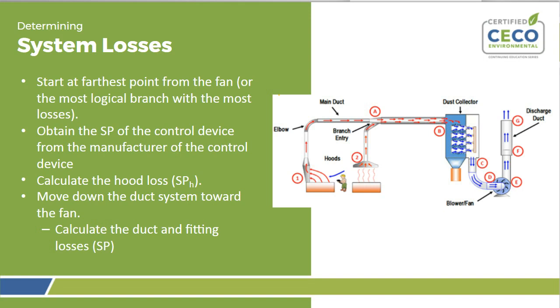It goes out of the clean air plenum of the dust collector into your fan, from your fan to your discharge stack, which in this case is a no-loss stack head. At that point, you have the total static pressure for your system. You know what Q is, your volume. You can contact your fan guy, give him those 2 numbers, tell him what accessories you want for that fan, and within minutes, because it's all computerized, he can give you the price for the fan you need for your system.